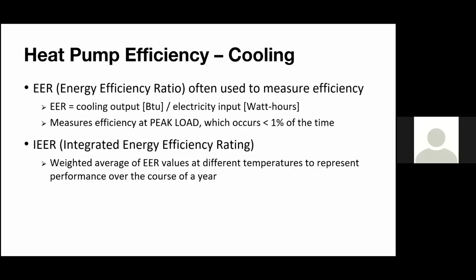Peak load at 95 degrees, even though we had those humid days a couple of weekends ago at like 95 degrees, normally that's only about 1% of the time in Boston. So if you think about it, that's good for conventional equipment, but at the end of the day, it's not telling the full story of variable speed compressors. So you actually might look at 2 labels. You have a conventional piece of equipment and a heat pump sitting next to each other. You might look at the label and say, all right, the EERs are relatively the same number. And those of you who may not be completely familiar with efficiencies might go, okay, these are pretty much the same efficiencies. Why don't we just go with the cheaper option? It's going to work the same. And that is not the case, because peak load is actually the least efficient point in a system, right? So it's not telling that full story.